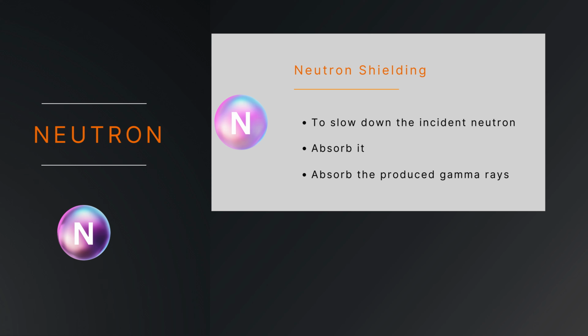In radiotherapy, when 10 MeV or above is used in the treatment, there is a probability that neutrons are produced. For most stable nuclei, the binding energy for the neutron is around 7 to 10 MeV. So, when photon energy is high enough, i.e. 10 MeV or higher, the photon might interact with the nucleus and produce neutrons. So, it is important to take into consideration the neutron shielding if you are designing a bunker for a linear accelerator that can generate photon beams with energy of 10 MeV or higher.